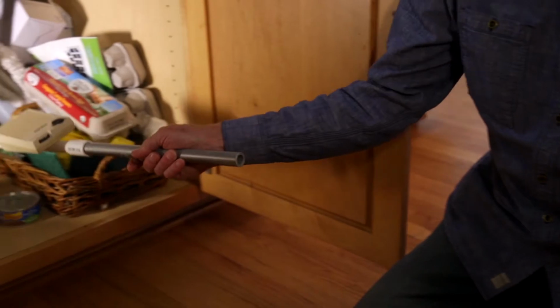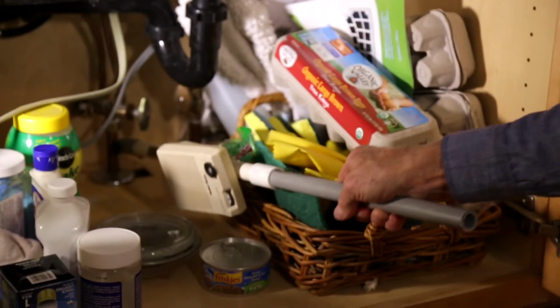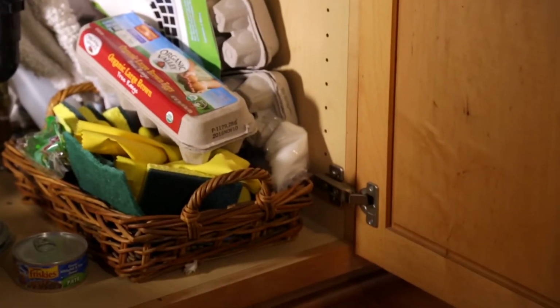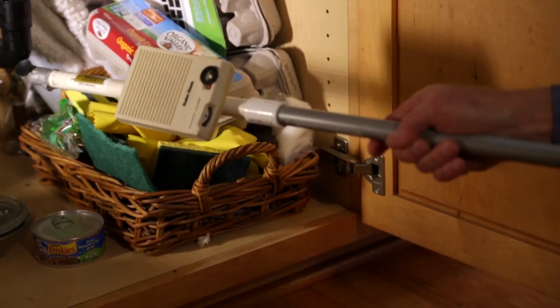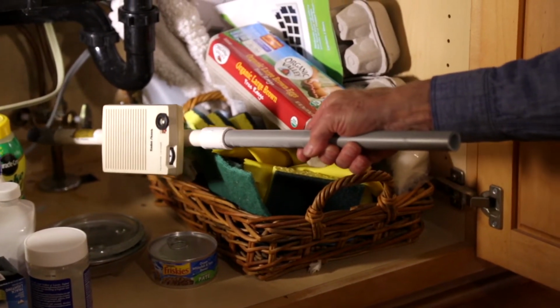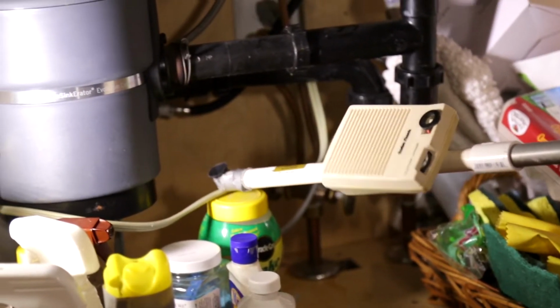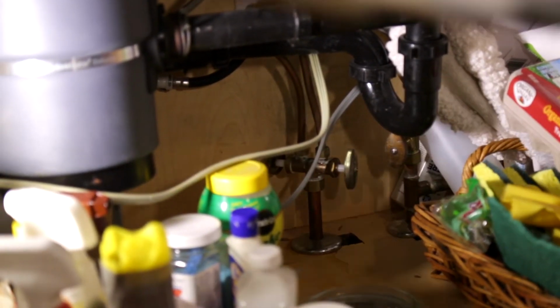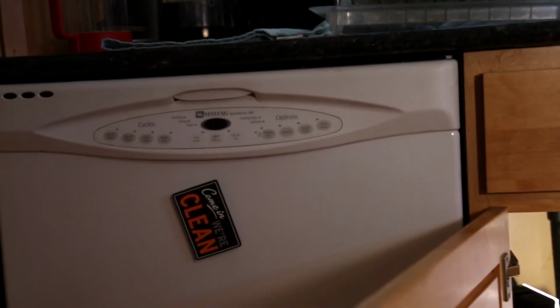And we discovered that with the use of our trusty buzz stick in the kitchen cabinet: the current flow is coming up the water pipe into the kitchen cabinet, and we noted that it is not going to the garbage disposal, and that's what this line is for, but we did find it going to the dishwasher over here. And it goes to the dishwasher because the dishwasher is connected to the electrical system through its power cord, and that's grounded, and the grounding hooks up to the frame of the dishwasher, which touches the water piping, and so we have a complete circuit, and the current flow can be going through the dishwasher and then back to the power company by way of the ground lead on the dishwasher.